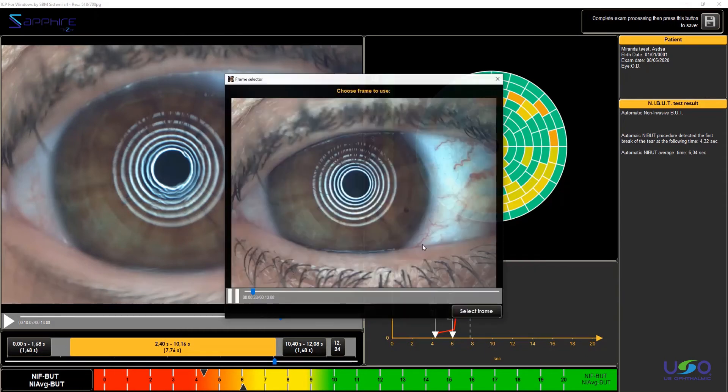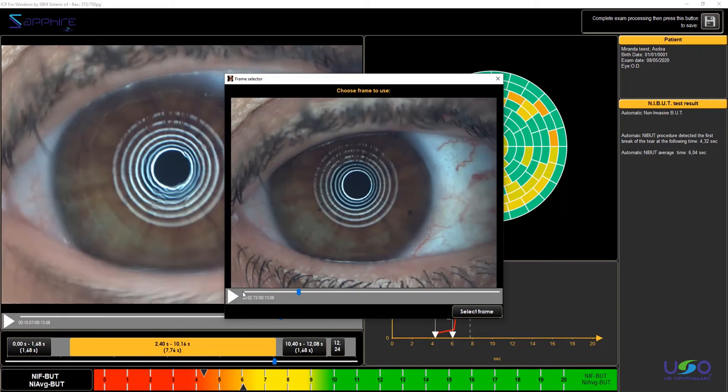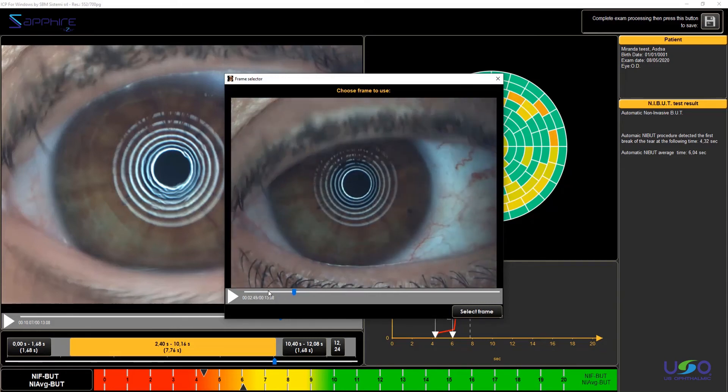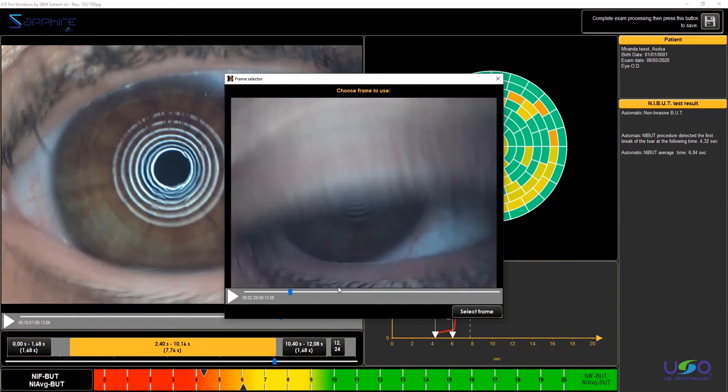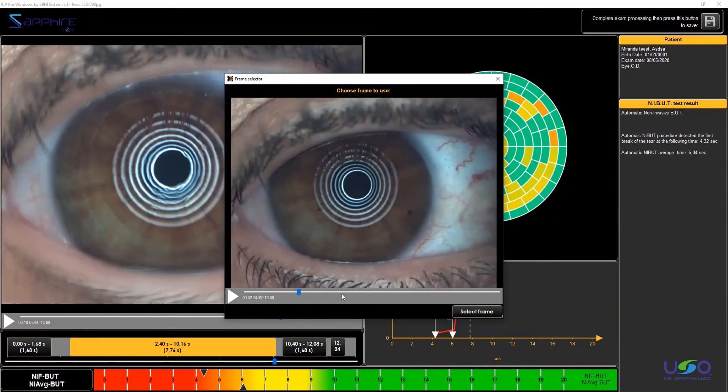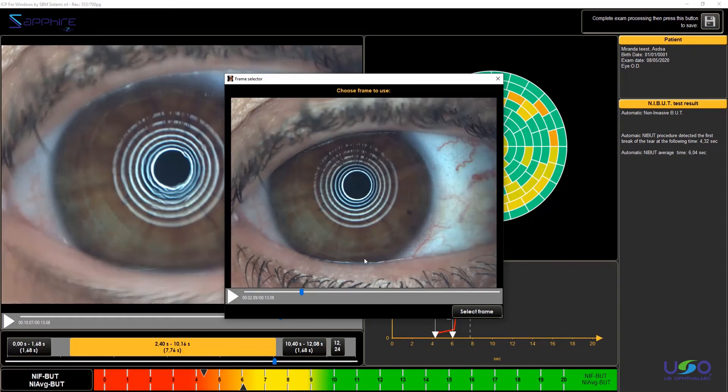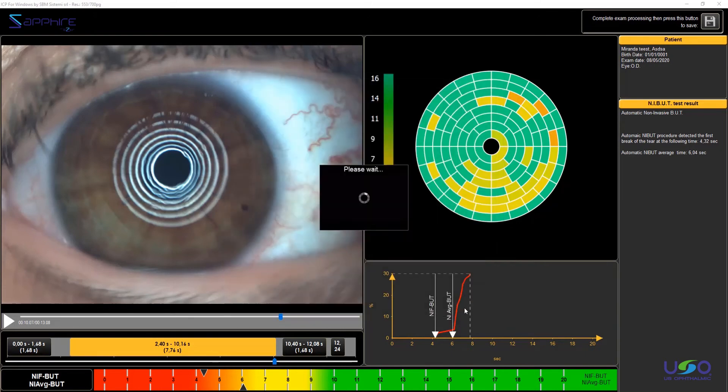I push on Yes, and now the software asks you which frame you want to grab from the video to do this analysis. Which one to select? Our suggestion is to select the frame immediately after the opening of the eye. Because in this way, like this frame, we are sure that the tear is well disposed and that there are no false positive results due to any breaking or to any water that fell down by the cornea and increase the tear meniscus volume. So this frame is good, I just push on select frame.